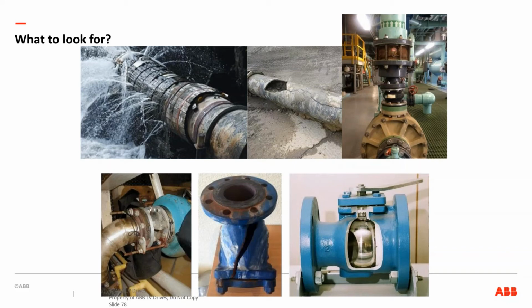There's the connection between the pipes, and there's the repercussions of the constant hammering of the water cycling on and off and on and off, instead of using the constant pressure type of application. I talked earlier about starting and stopping the motor and then making it shift and offset. You can see here we have a little bit of rust up here from some drainage, but you'll notice that this is kind of skewed. This is coming down straight here, and this is shifted over about an inch or two. And that's because that pump is starting across the line.